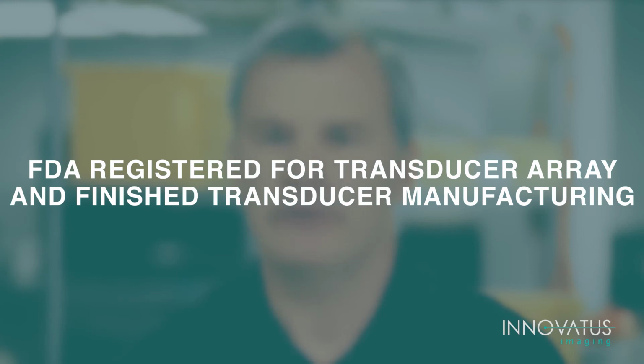In support of our array manufacturing for both OEMs and the repair industry, we use semiconductor dicing saws to manufacture the tiny elements that are critical to the function for ultrasound transducers. These saws can dice kerfs that are fractions of a human hair in width and ensure accuracy of microns over the length of the array. This is critical to the function of the array to ensure proper image quality over the life of a product. This level of accuracy is critical for us to ensure that over time our arrays perform as expected and provide world-class image quality.